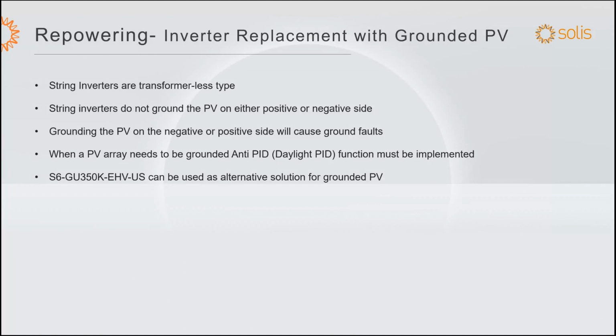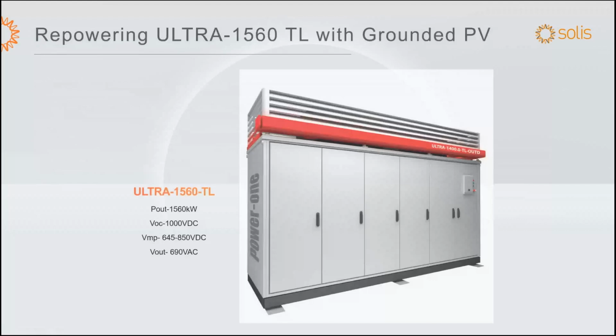That function was touched on a little bit earlier. What it does is shift the ground potential to the minus PV potential. That way, it effectively has the same effect on the module as grounding the module. And our 350 kilowatt uses the anti-PID, which is PID daytime, not to be confused with anti-PID recovery, as an optional feature.